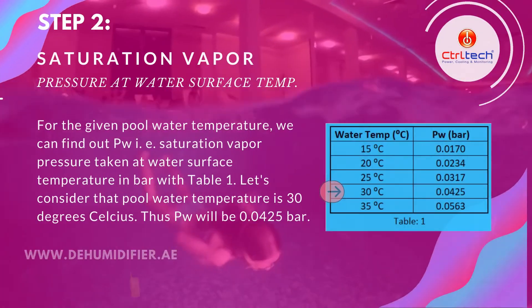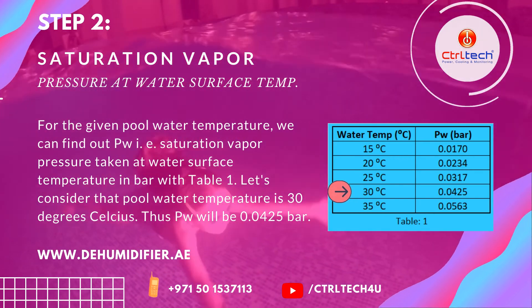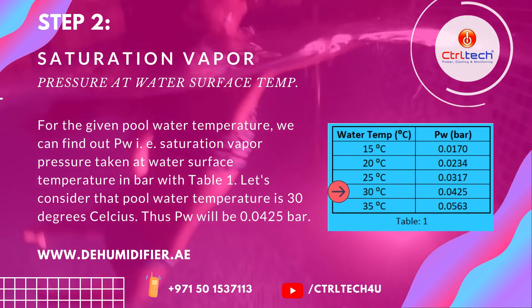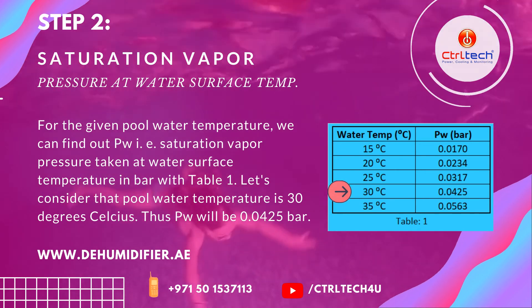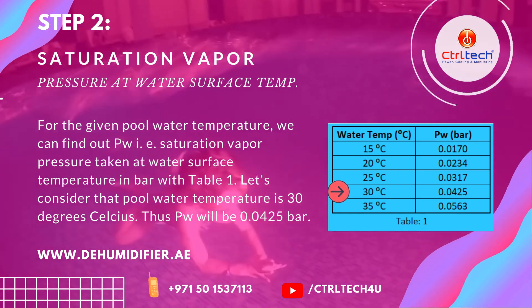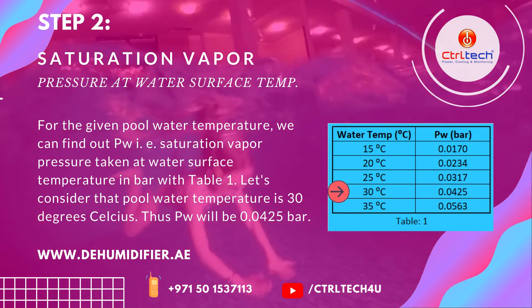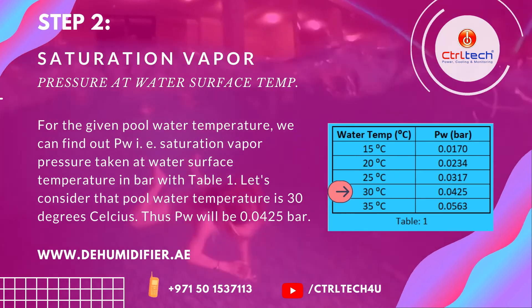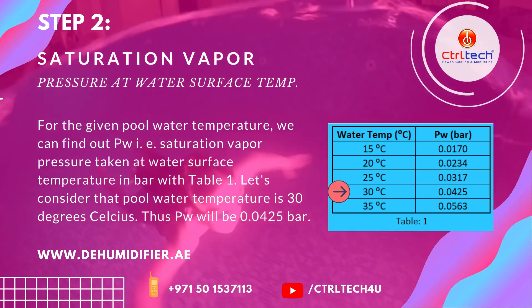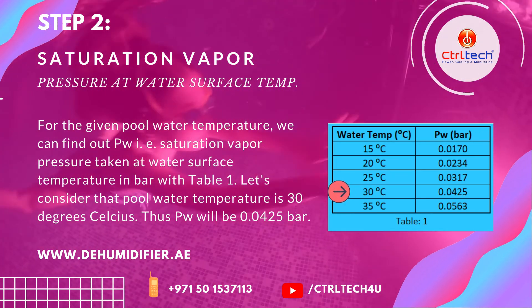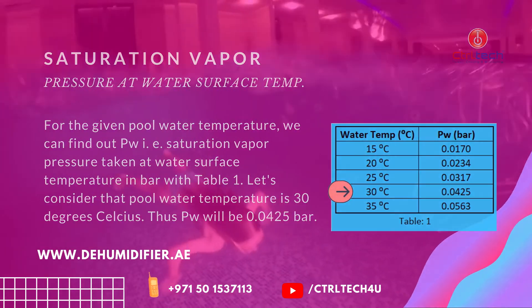Now let's find out PW. For the given pool water temperature, we can find out PW, i.e. saturation vapor pressure taken at water surface temperature in bar, using Table 1. Let's consider that the pool water temperature is 30 degrees Celsius. Thus PW will be 0.0425 bar.